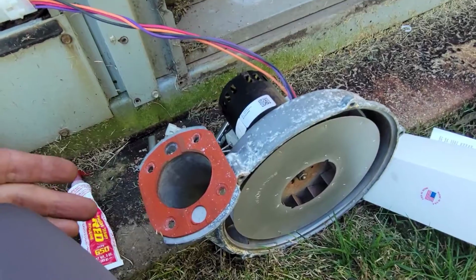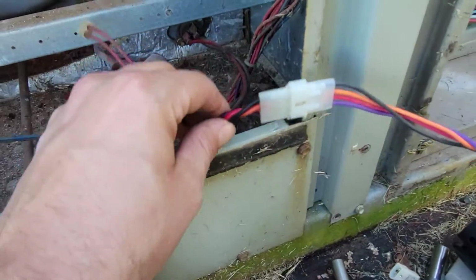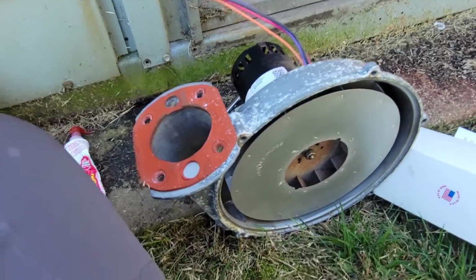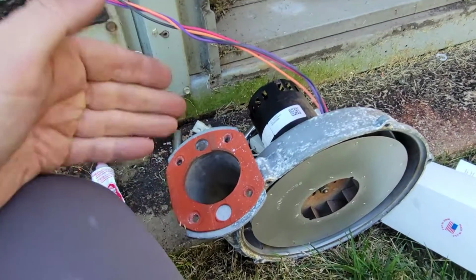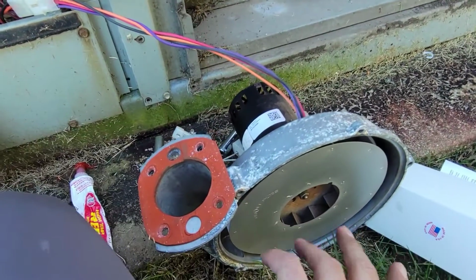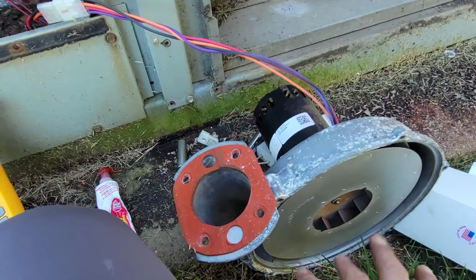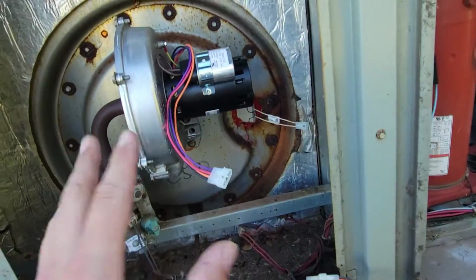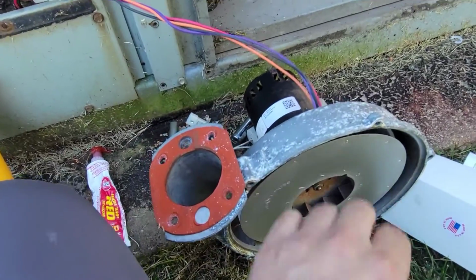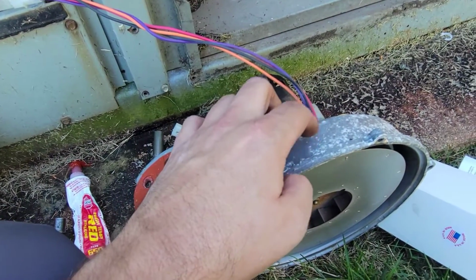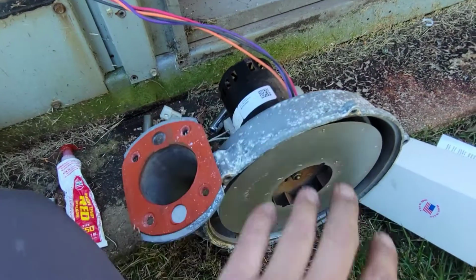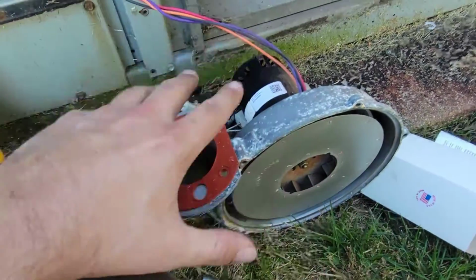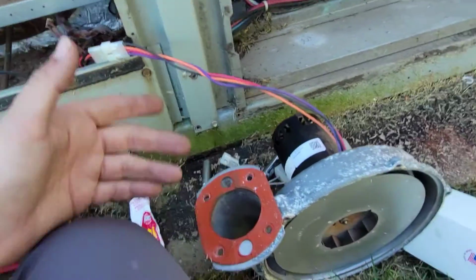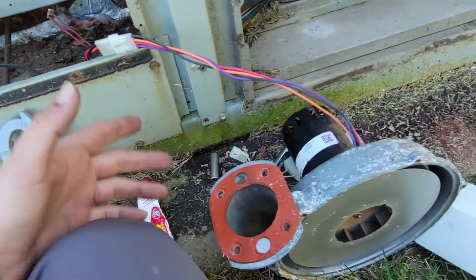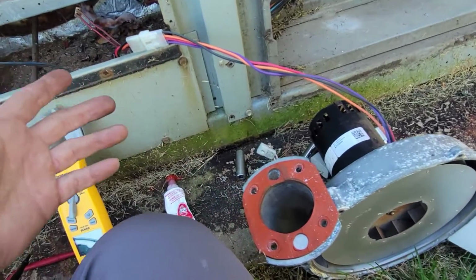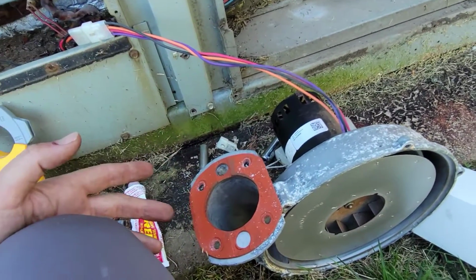All right, this is the old motor. You can see it is plugged in now and it's doing nothing. So the only way you would know this motor is bad, because usually on these inducer assemblies the wheels are burned up, not on these models, but on residential models especially, your inducer assembly housing is made out of thinner material than this, and it's rusted through and you can tell it's bad. But this, you need to use your meter. You need to ohm the windings. If you get an OL reading and you're not reading resistance, you have an open circuit.